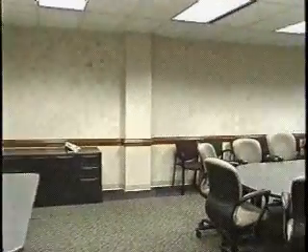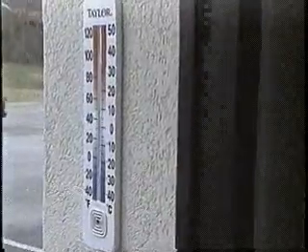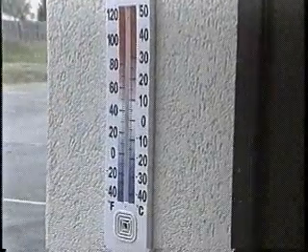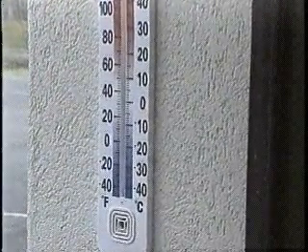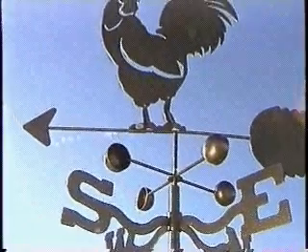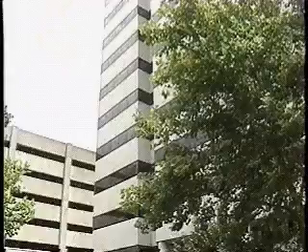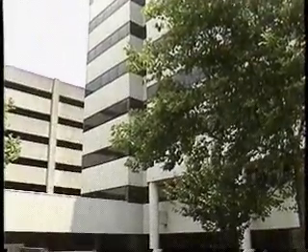The air exchange rate will vary depending on the shelter's volume, the tightness of the doors and windows, the existence of vertical routes such as chimneys, flues, and elevator shafts, whether heating, ventilation, and air conditioning systems are operating, the indoor-outdoor temperature differences. The greater the difference, the higher the infiltration rate, wind speed and the orientation of the building to those winds, as higher wind speeds increase the infiltration rate, and the sheltering of the structure by surrounding trees and buildings.